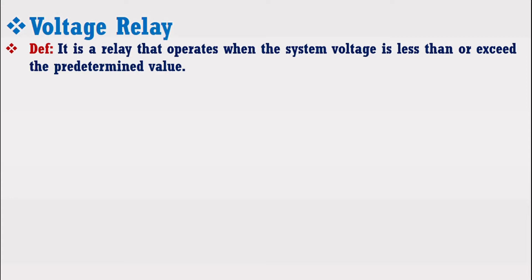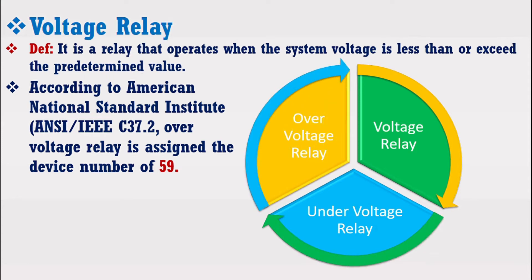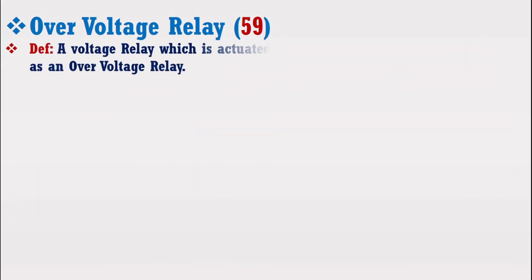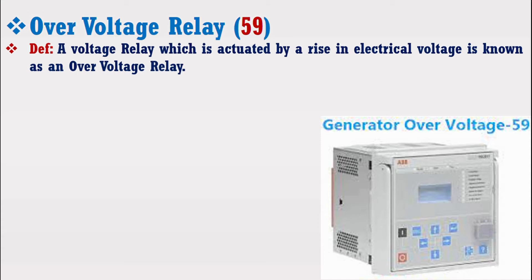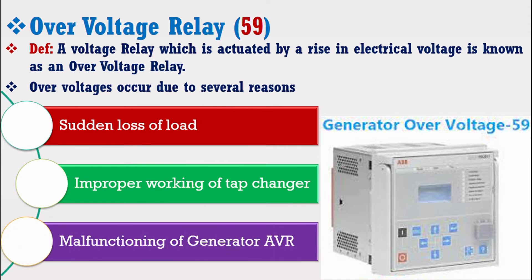A voltage relay can be defined as a relay that operates when the system voltage is less than or exceeds the predetermined value. According to the American National Standard Institute and IEEE Standard C37.2, the overvoltage relay has been assigned device number 59. Voltage relay has two types: undervoltage relay and overvoltage relay. A voltage relay which is actuated by a rise in electrical voltage is known as an overvoltage relay. Overvoltages occur due to several reasons like sudden loss of load, improper working of tap changer, and malfunctioning of generator AVR.